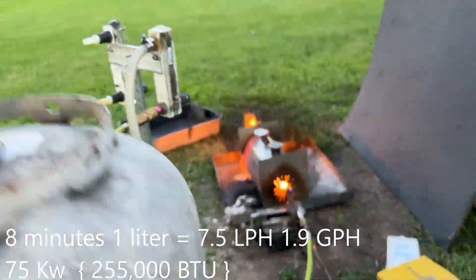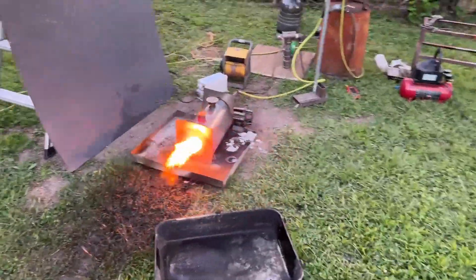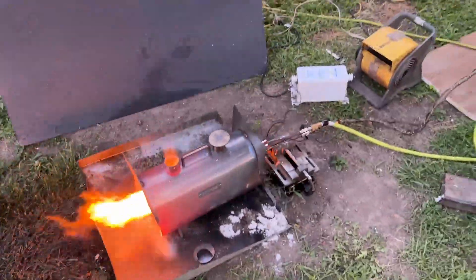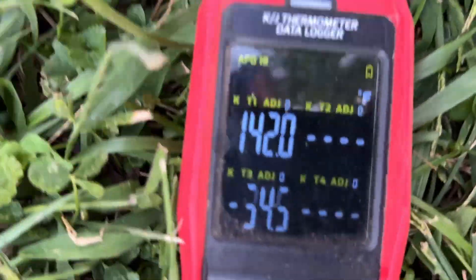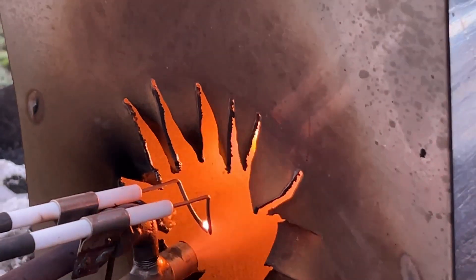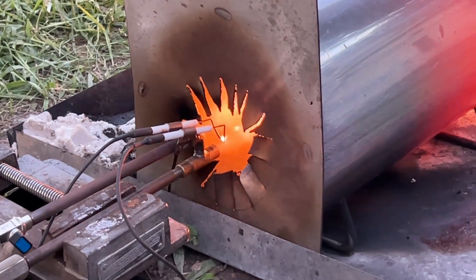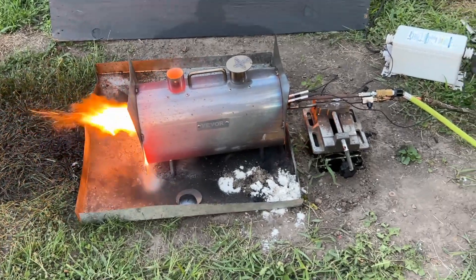Eight minutes. So it runs without the preheat, but it ain't very happy about it. Probably at 120 — nope, that's way off. Even 140 has it kind of waning. That compressor ain't hardly running at all. Fireball is further forward in the unit because the fuel isn't as volatile. You can clearly see it — we lost two inches of fireball. 140 degrees.